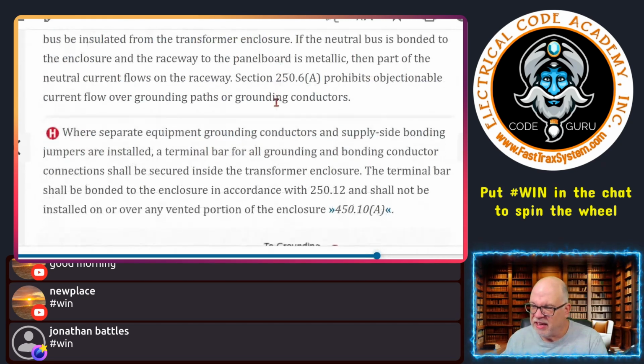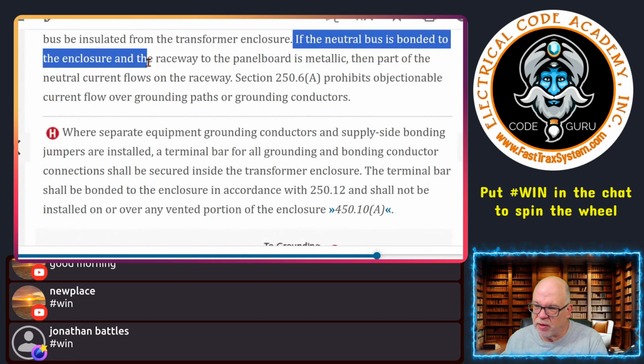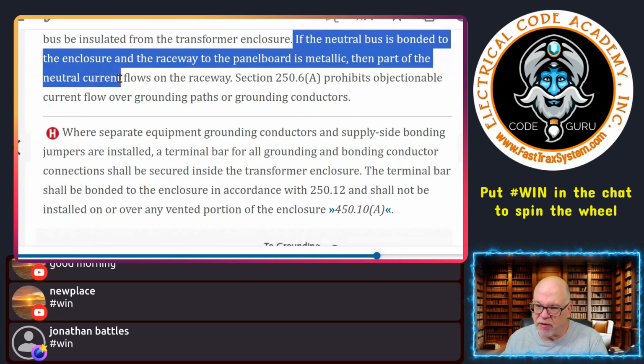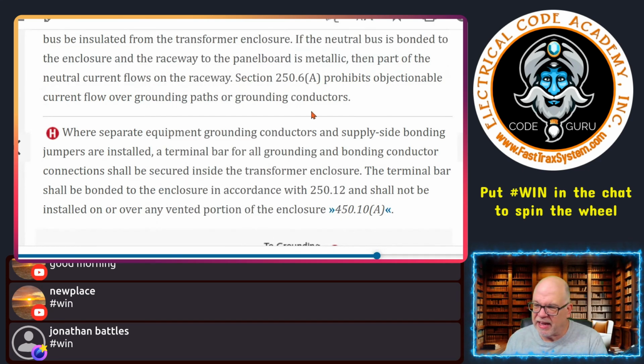Then it says, if the neutral bus is bonded to the enclosure and the raceway to the panelboard is metallic, then part of the neutral current flows on the raceway. And again, that would be prohibited because that creates objectionable currents that can cause current to flow in paths that were unintended, but it can also cause it to flow on paths that you could come in contact with that are part of the grounding and bonding system.